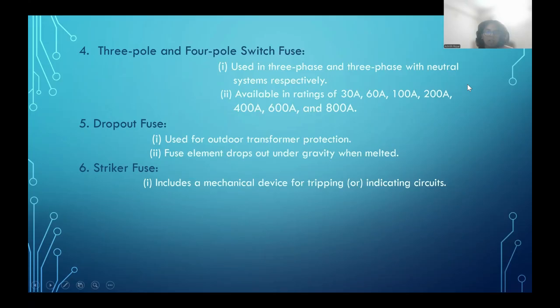The fourth type is three pole and four pole switch fuse, used in three phase and three phase with neutral systems respectively. Available in ratings of 30 amperes, 60 amperes, 100 amperes, 200 amperes, and so on till 800 amperes. The fifth type is dropout fuse, used for outdoor transformer protection, where the fuse element drops out under gravity when melted. The sixth type is striker fuse. It includes a mechanical device for tripping, indicating the circuit.